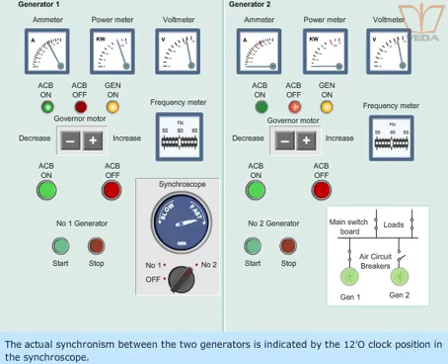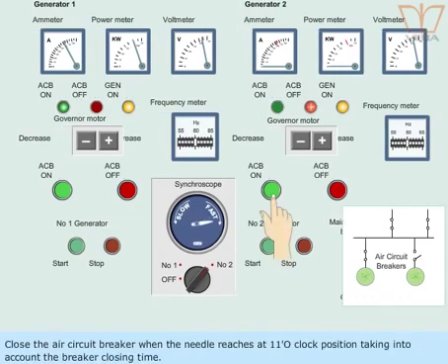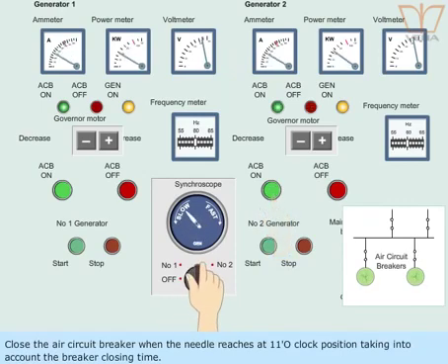The actual synchronism between the two generators is indicated by the 12 o'clock position in the synchroscope. Close the air circuit breaker when the needle reaches at 11 o'clock position, taking into account the breaker closing time.